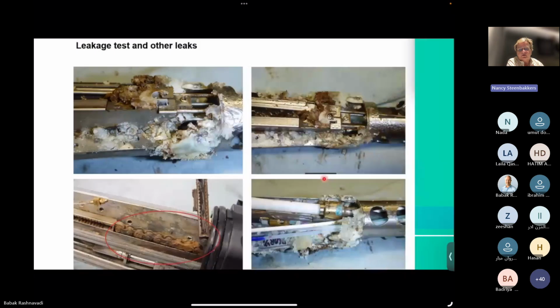So that's what I want to show you. This is really from the endoscopy nurses from Europe. They are also showing these pictures, because leak testing at the moment is always performed in the wrong way. You have your leak test pump, and Olympus, for example, or also Pentax, mention you have to drown the endoscope in the water to perform the leak test. This is totally wrong, because then you get those kind of situations.